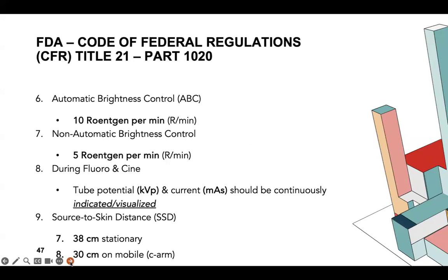Then it also tells us about our automatic brightness control. Basically, remember, automatic brightness control is what takes over after our kV and mA max out, when the machine is giving all it can give. It's maxed out the technique. So your ABC takes control. It tells us that should be no more than 10 roentgens per minute. It tells us our non-automatic brightness control should be no more than 5 roentgens per minute.